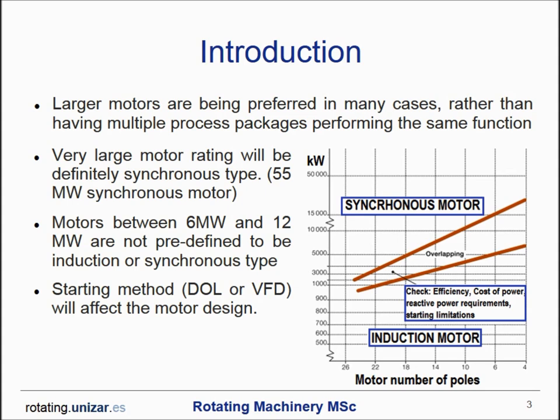For the oil and gas industry, electric motors are becoming more and more critical. When dealing with high-power motors, reliability and efficiency are two things that are carefully evaluated. Furthermore, larger motors are being preferred in many cases rather than having multiple units performing the same function. For example, a 55 MW motor was built to be used in an oil and gas facility in Africa — a motor of this size will definitely be a synchronous motor. On the other hand, motors of smaller rating, say 6 to 12 MW, are not predefined as induction or synchronous, and this selection is what this module will address.